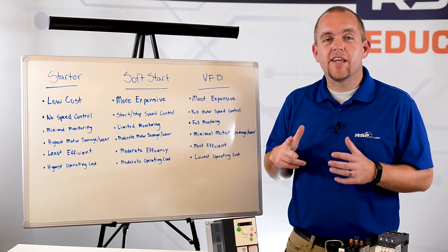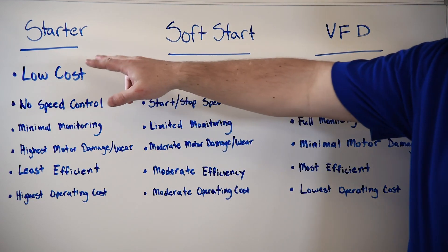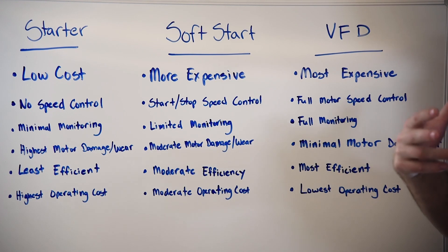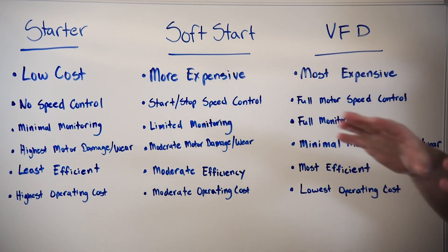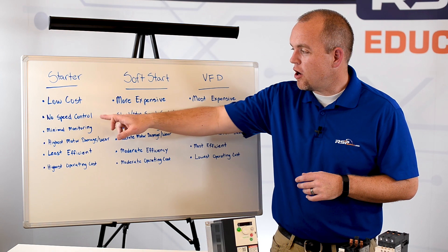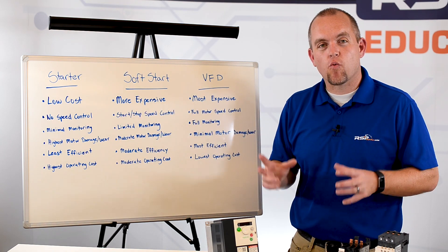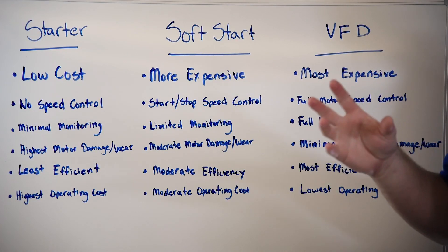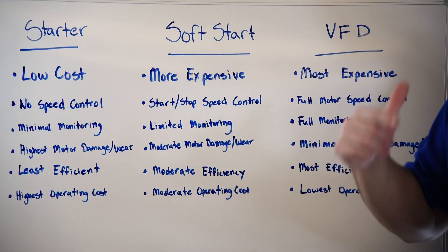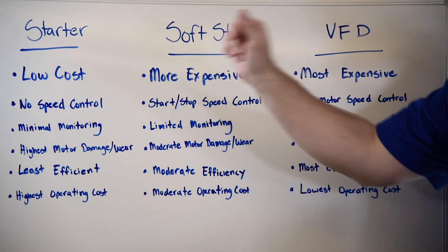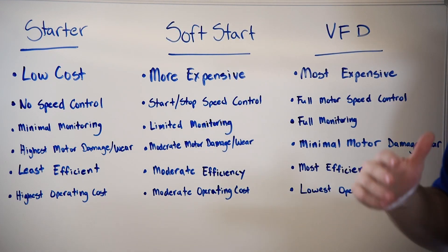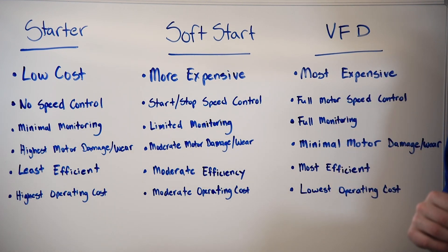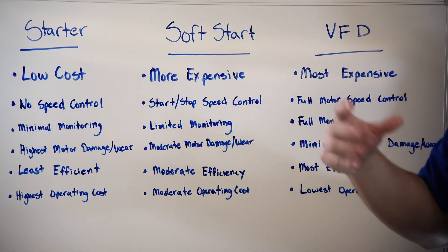Now let's compare the three different options. First, we have the starter, which is going to be the lowest cost option, all the way up to the VFD, which is going to be the most expensive, with the soft starter falling somewhere in between. Starters offer no speed control — they ramp up quickly and stay at full speed the whole time they're running. Soft starters give us a gradual ramp up in speed until they get to full speed, then operate much like a starter. A VFD gives us full motor speed control, allowing us to ramp up and down during the start and stop as well as the full run cycle.